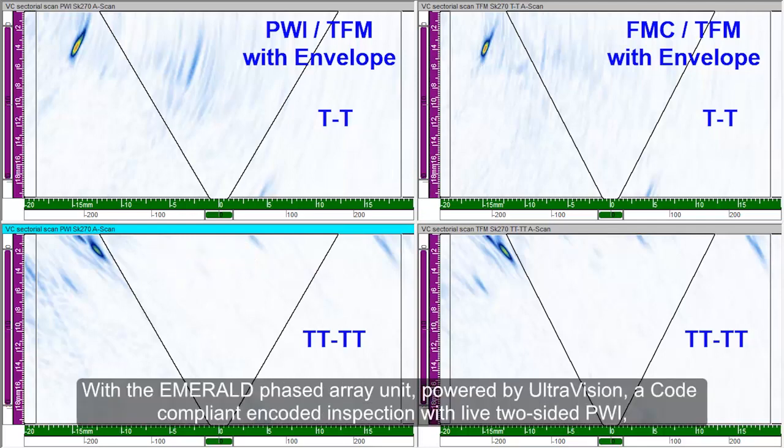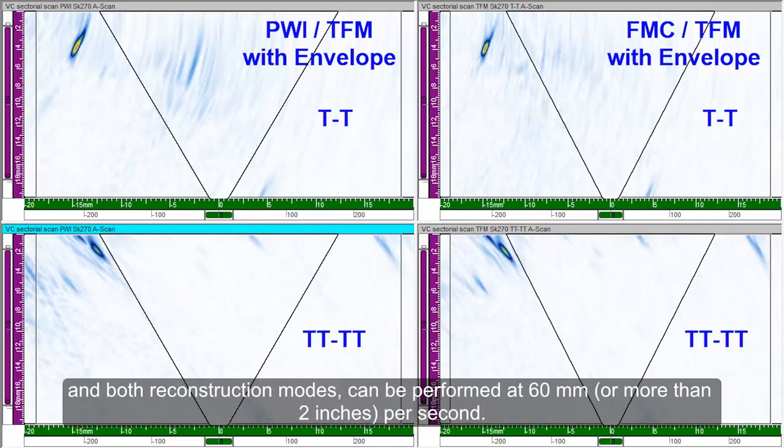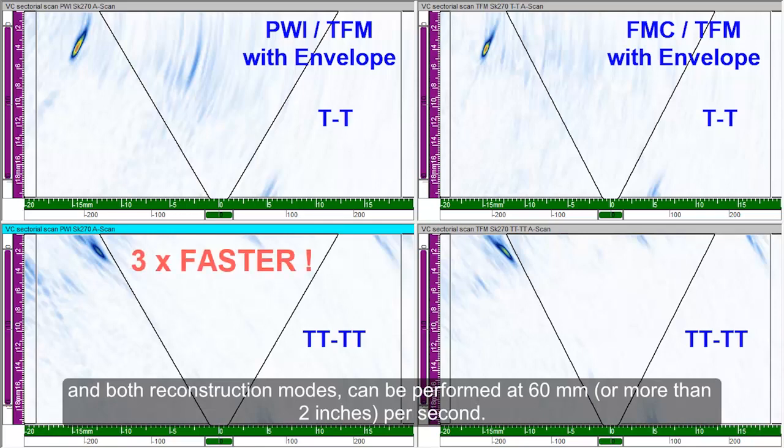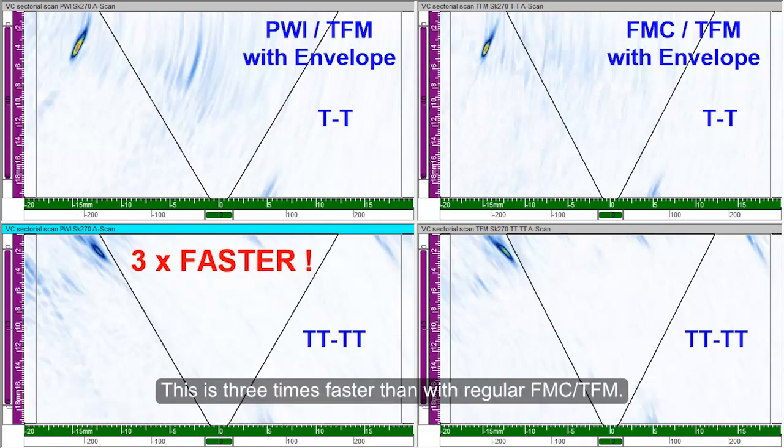With the new Emerald phased array unit powered by UltraVision, a code-compliant encoded inspection with live two-sided PWI and both reconstruction modes can be performed at 60 mm or more than two inches per second. This is three times faster than with regular FMC TFM.